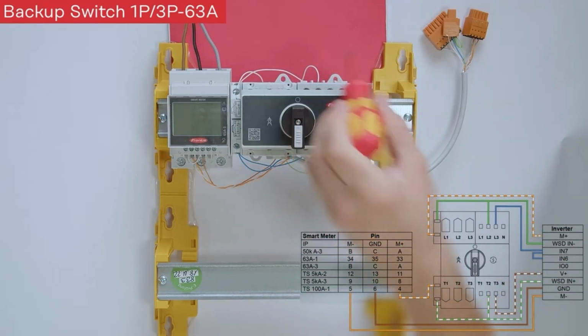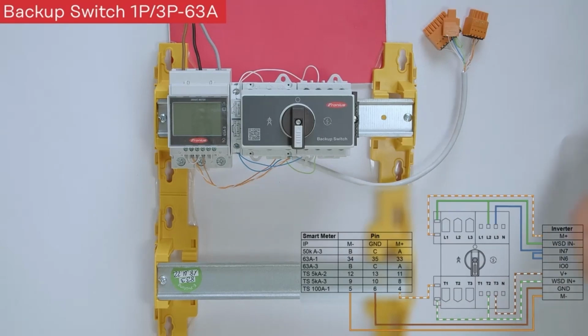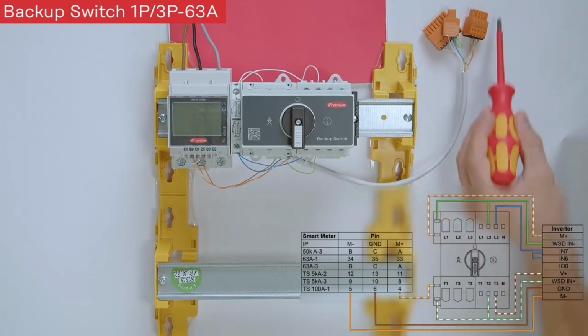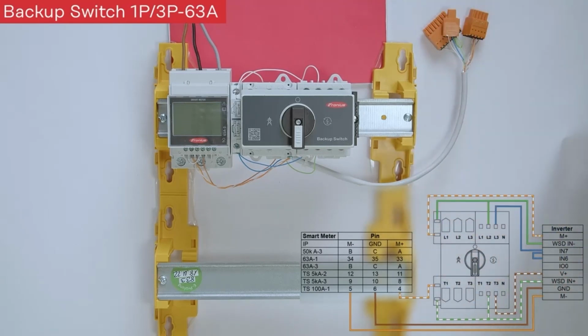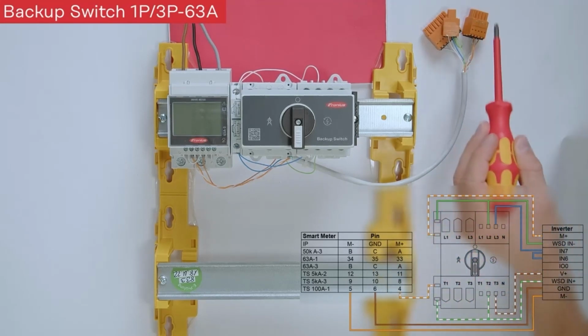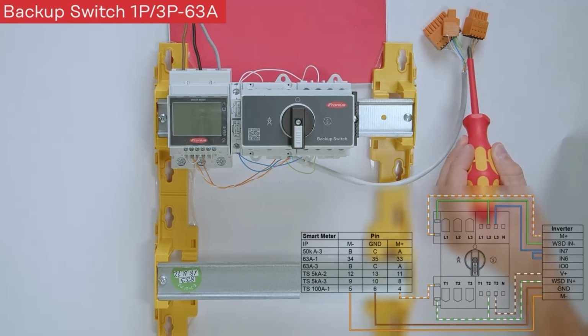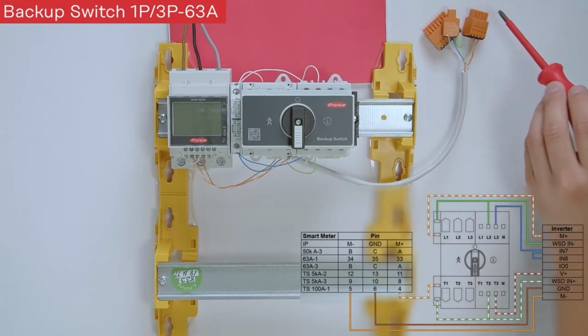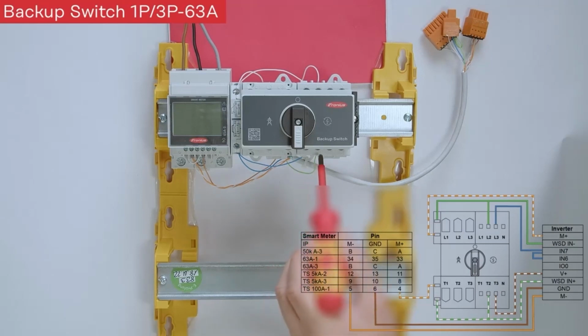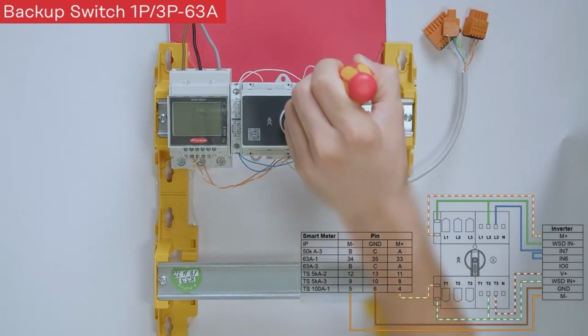Last but not least, we need to install I6 and I7, our digital inputs on the inverter, and therefore we need to close I6 and I7 with our plus 12 volt signal on the Fronius inverter. So on the data communication side of the Fronius inverter, you will find the plus 12 volt signal as well as input 6 and input 7. And to make installation easier, you can build a cable bridge between I6 and I7 directly on the inverter, and then with one line you go directly on L2 on this contact here to close I6 and I7 with one single line.